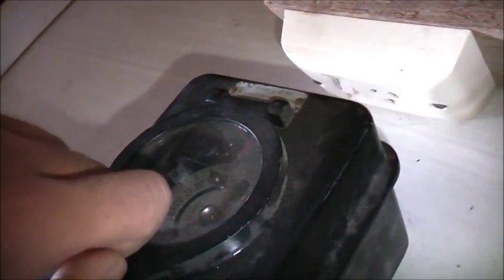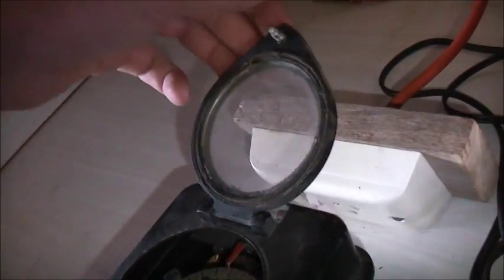I just put it on a table carefully and bumped it slightly and the escapement is working. So I'm going to give this thing a good lubrication, a good check over it before I power it up. Property of the State Electricity Commission of Victoria, time switch number NE - North East - 509. It's a pretty unique time switch, this one.